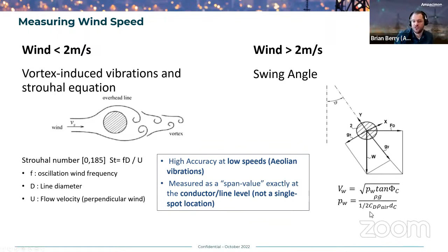As I mentioned, we need the conductor temperature, we need to know the wind speed, and from that and other models, we can essentially get the ampacity, the amount of current I can push through the line. I can take the weather measurements, line measurements, apply algorithms based on IEEE models, and use forecasted weather data from third-party weather providers. So I can tell you not only what's happening right now, but what's happening tomorrow.